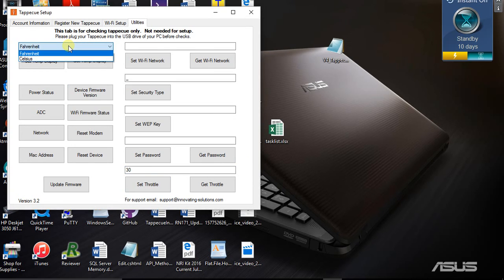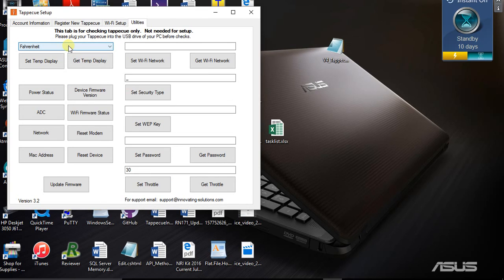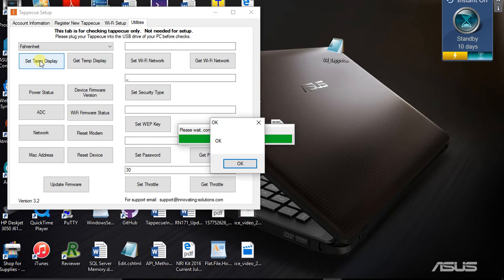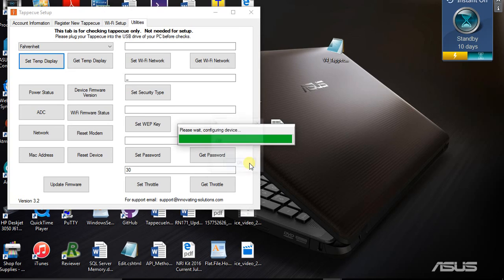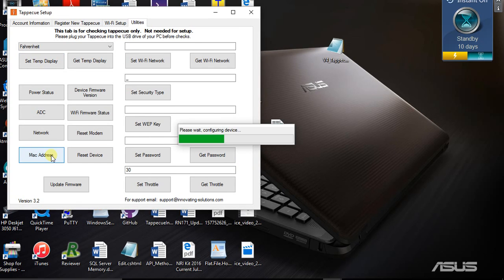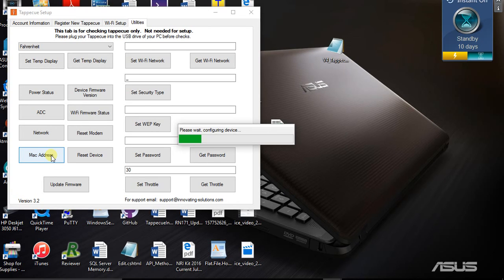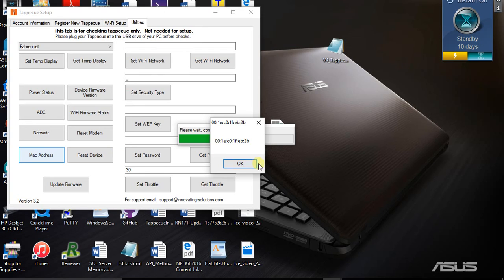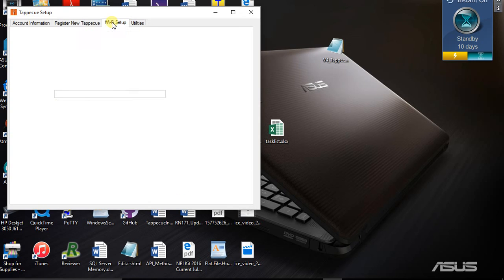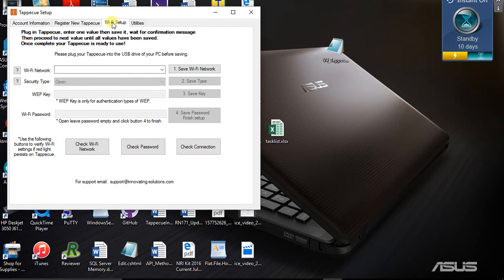Then you're going to select whether you want Fahrenheit or Celsius, and hit Set Temperature Display. What that does is it says what temperatures do you want displayed on your Tappecue. I want Fahrenheit. Then I'm going to click the MAC address button. This just sets the MAC address of your Tappecue into the memory of the Tappecue so that it can send temperatures faster.